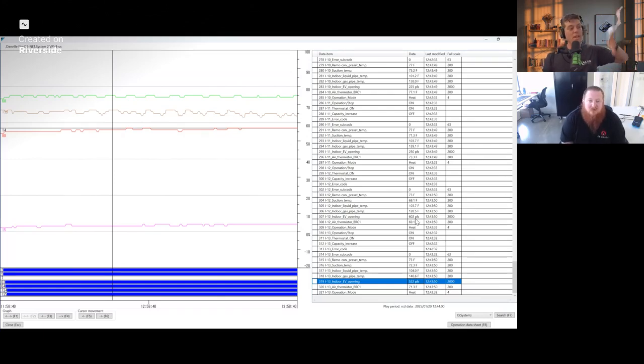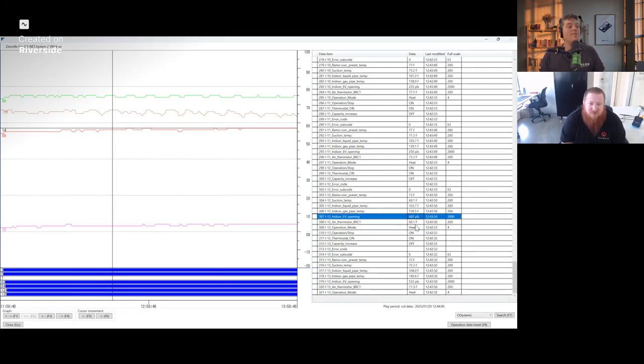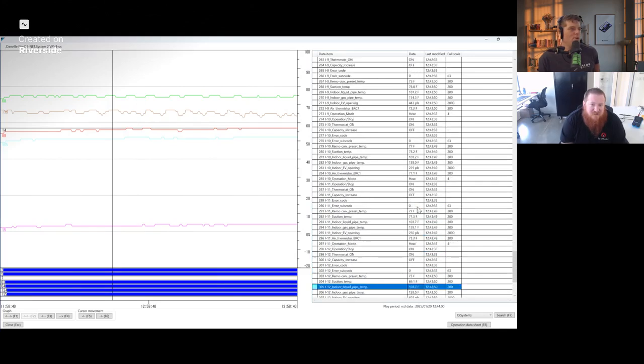He wants to go to the indoor unit that has the most pulses, which I think was 602, right? That's the biggest. Yes. And so he wants to see where the most refrigerant should be flowing. What does it look like? All right, so we got 103 over 128. And what's our condensing temperature? All right, he wants to know. Put it on the board, Johnny. Da-da-da-da. 103? 103, yeah.